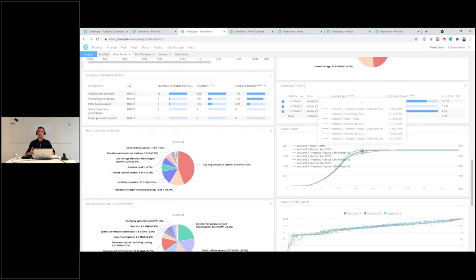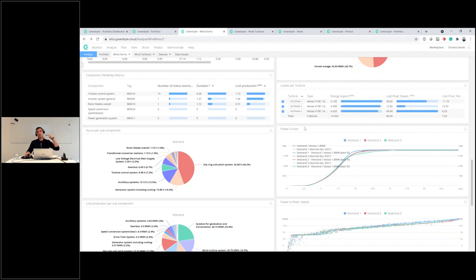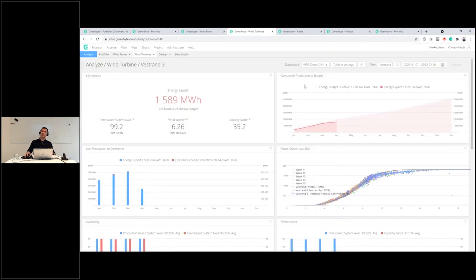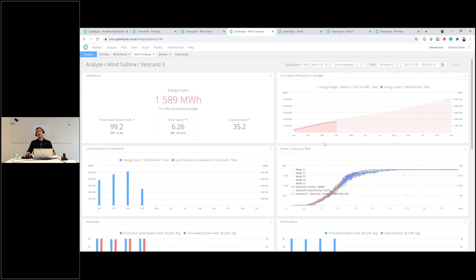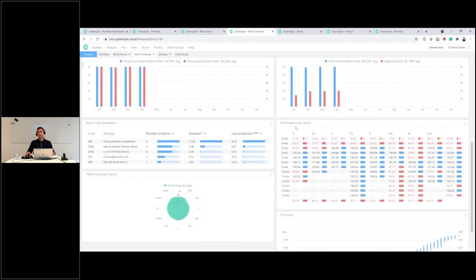If we look at performance, we can start from something as basic as plotting the power curves, which many of you may already be familiar with. For example, turbine 3 in this small wind farm of three turbines is performing below the other two. Same way we went from portfolio to wind farm and from wind farm to wind turbine level, we go to turbine number three for a closer look using smarter visualizations — a colored scatter per week, or performance per wind speed bin and per sector. The performance seems to be lagging from the southwest compared to the southeast wind direction.